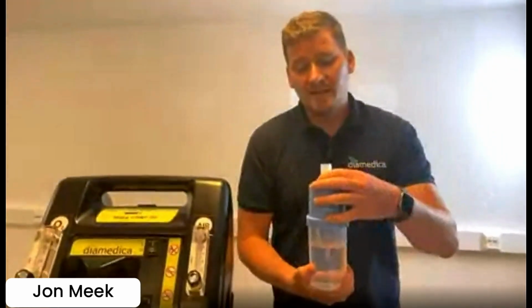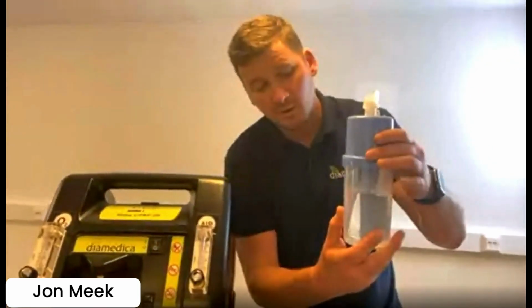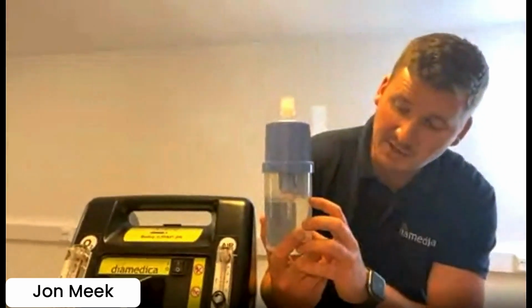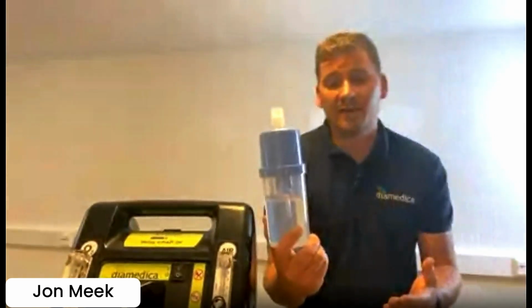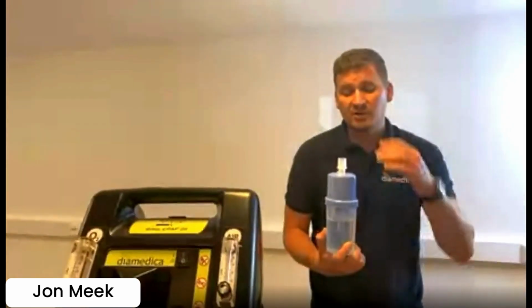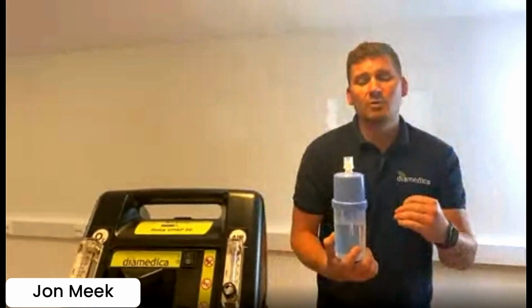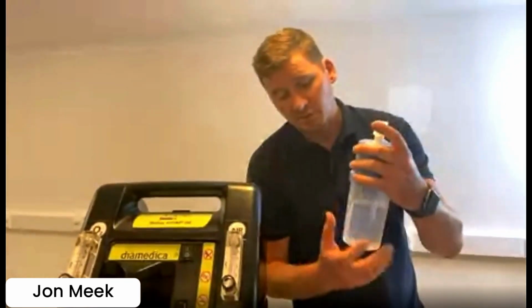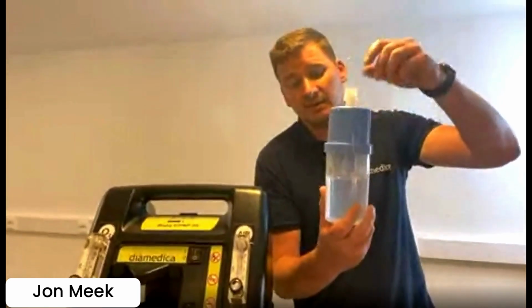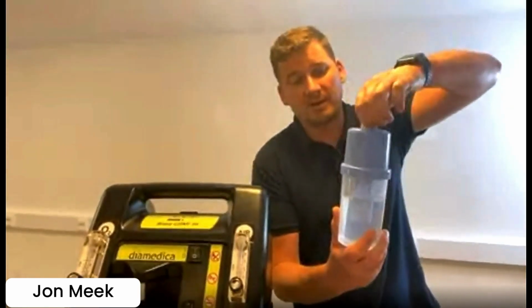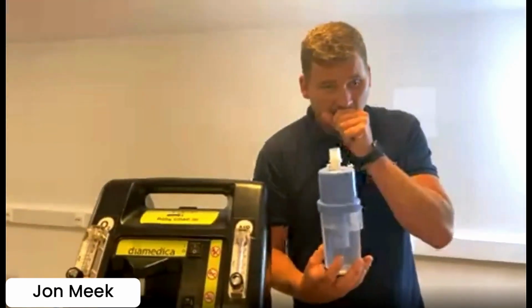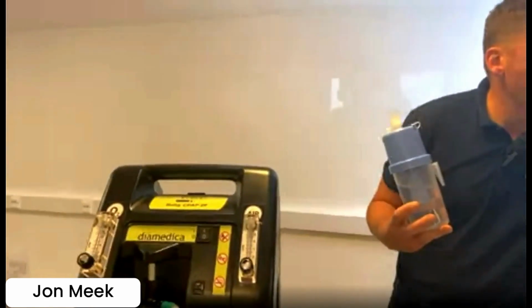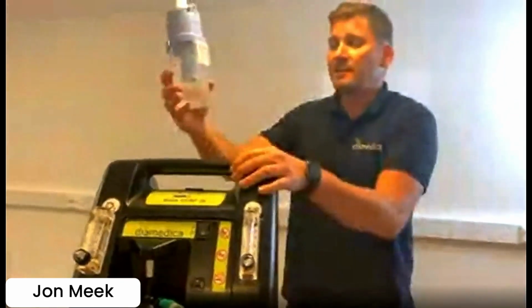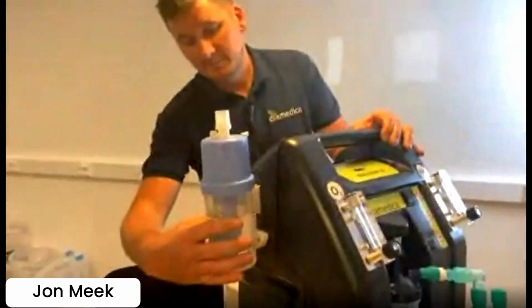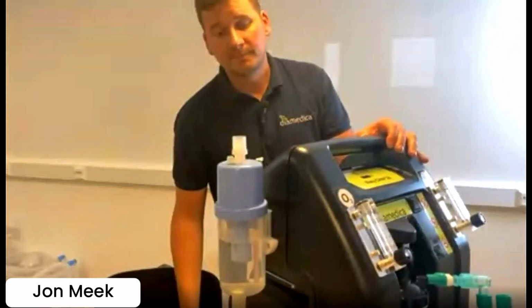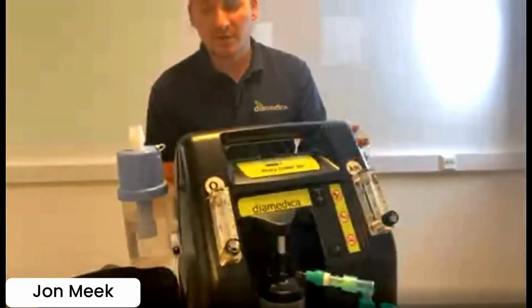What's also really important is knowing that the water level is the correct level. So when you fill this, it must be at the correct level. There's a dotted line. If you overfill it, you'll be providing higher pressure than what you set. If you underfill it, you'll be providing lower pressure. So it's really important to fill it to the correct level when it's set to 0, and then you'll be providing the correct level of CPAP to the patient. Excuse me. So the bubble bottle will fit on the side of the machine like so. Nice and simply slots onto the side there.